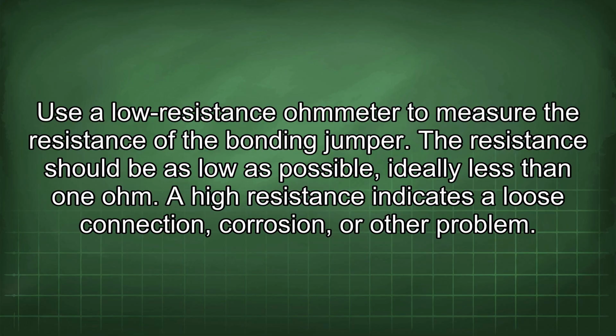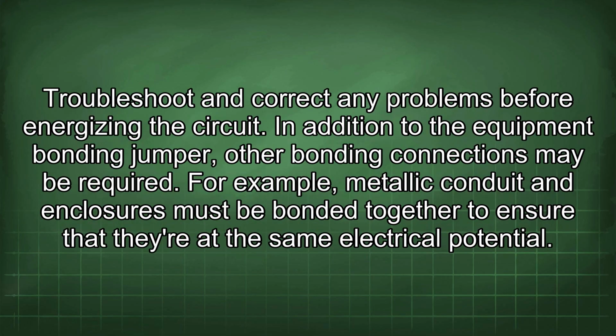The resistance should be as low as possible, ideally less than 1 ohm. A high resistance indicates a loose connection, corrosion, or other problem. Troubleshoot and correct any problems before energizing the circuit.